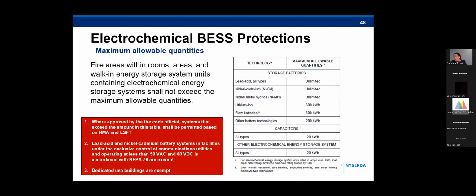There are two other exceptions: lead acid or nickel batteries under the control of communication utilities again, and dedicated use buildings. Also of note, lithium ion systems exceeding 600 kilowatt hours will need to go through the additional testing. If you are familiar with NYSERDA's model battery energy storage system law, this is the reasoning behind defining systems into those two tiers, over and under 600 kilowatt hours, with projects over 600 kilowatt hours having many more requirements to meet than those under 600.